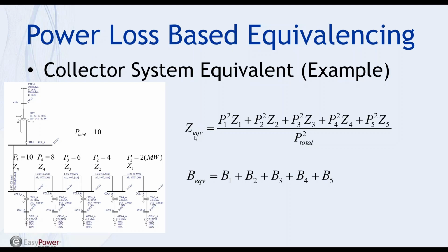So the equivalized impedance of the collector system equivalent would be the sum product of P squared times the impedance. Actually, the sum product of P squared and Z divided by the P total. And the charging of my collector system equivalent is actually the sum of all the charging of all the circuits, right? Straightforward. So we keep in mind those equations because we're going to use them later. What we need is the impedance of each circuit, which makes sense, and the active power flowing through the circuit.